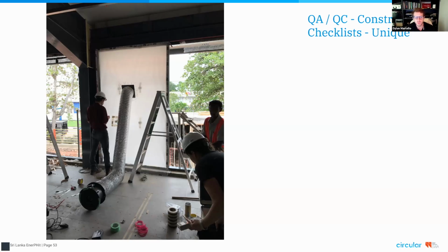So what we do is we have a little tiny fan, that's that black cylinder in the photo, and hook it up to a flex duct tube that connects to a plastic shroud creating an air chamber. We pressurize and depressurize that chamber to measure how much air is flowing through the assembly.